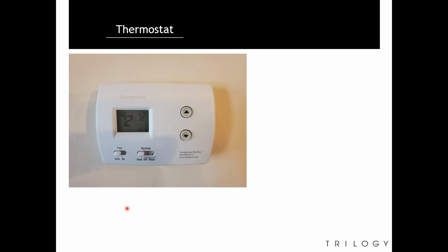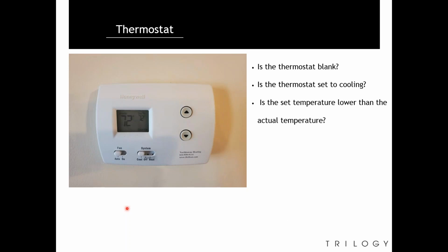So once we're on the inside, check the thermostat. Is the thermostat blank? Is the thermostat set to cooling? Is the set temperature lower than the actual temperature? Meaning, if it's 72 degrees set temperature and it's 73 inside the apartment, the thermostat should be kicking on and we should be cooling. Now, if it's 72 and its set temperature is 74, of course it's not cooling because that set temperature is not lower.